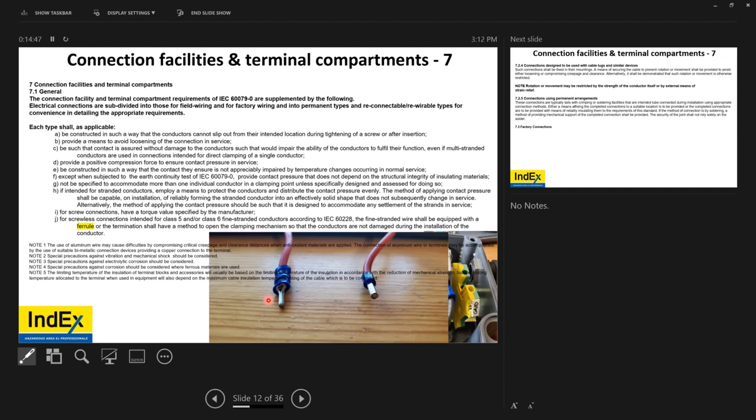If you really wanted to read through all this, what it says is for connection facilities for -7 for EXE, -15 for NA, -11 for intrinsically safe, -14, they'll call it a core end sleeve. Basically, your terminations have to be good like this. Shall be compact and square, not with damaged insulation like this, misshapen wires, misshapen core, misshapen insulation.